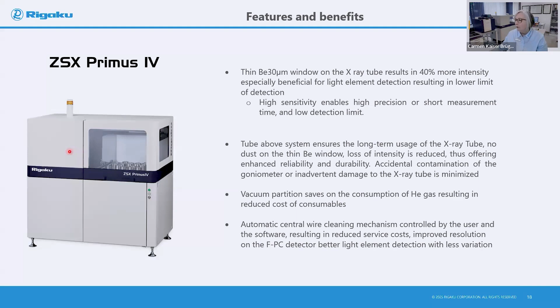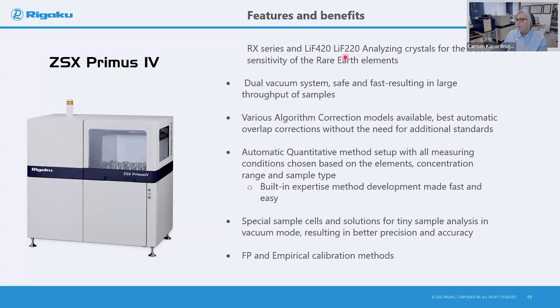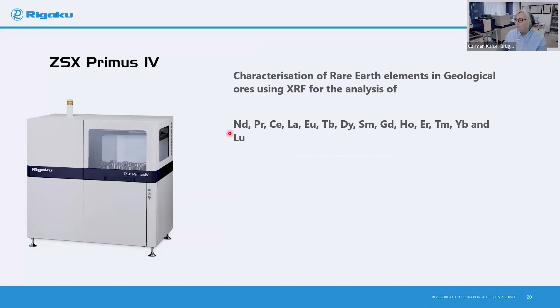So I will show you some examples of fundamental and empirical calibration methods to measure these kind of rare earth elements. And I will also give you some examples of these very special crystals that we have in our instrument, which are the Rigaku crystals, to give better separation and resolution of these rare earth elements, because they're very complicated. They have a lot of line overlaps. So in particular, we have the LIF420 and the LIF220, which will give you the best sensitivity. So let's look at these examples of some of these groups that you see here of rare earth elements.